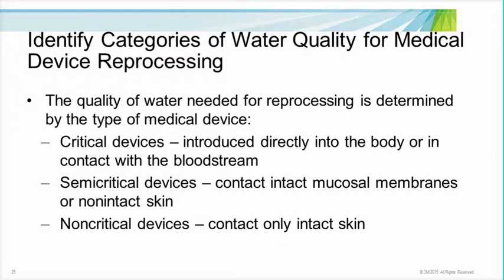Now, these devices, based on criticality, will define the reprocessing steps and the quality that is needed. For example, critical devices need to have a terminal sterilization process, and this really shows how important the final rinse and the water used for the sterilization process is, and that should be the critical water.